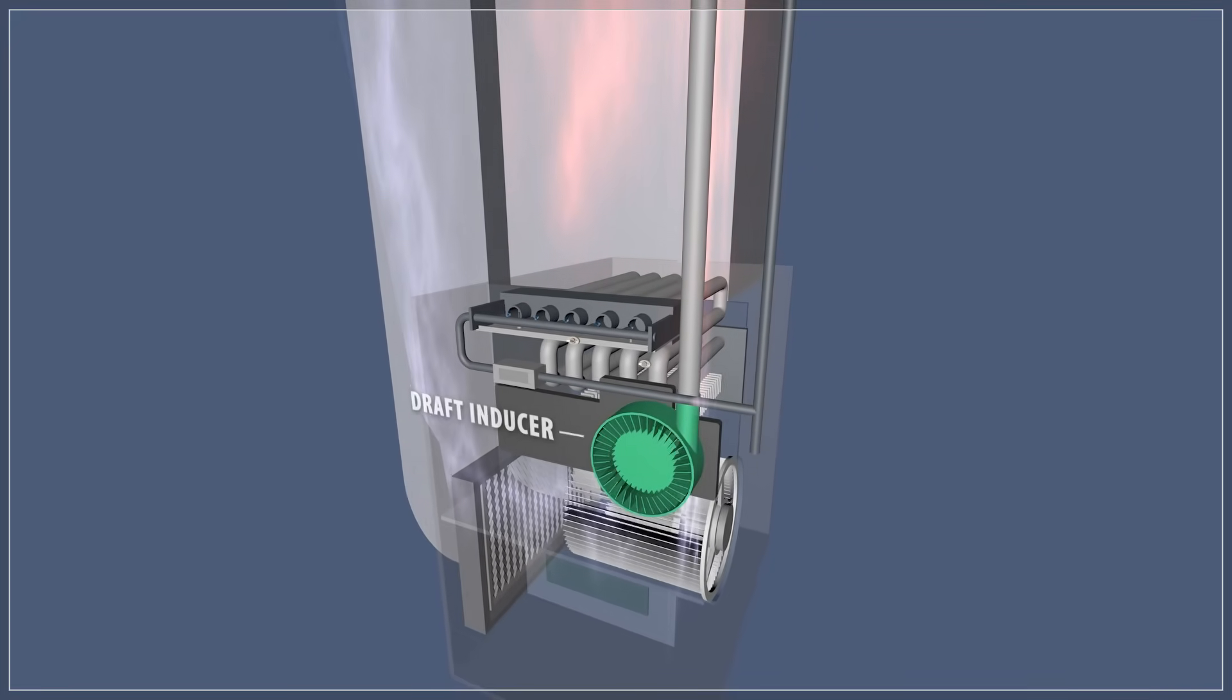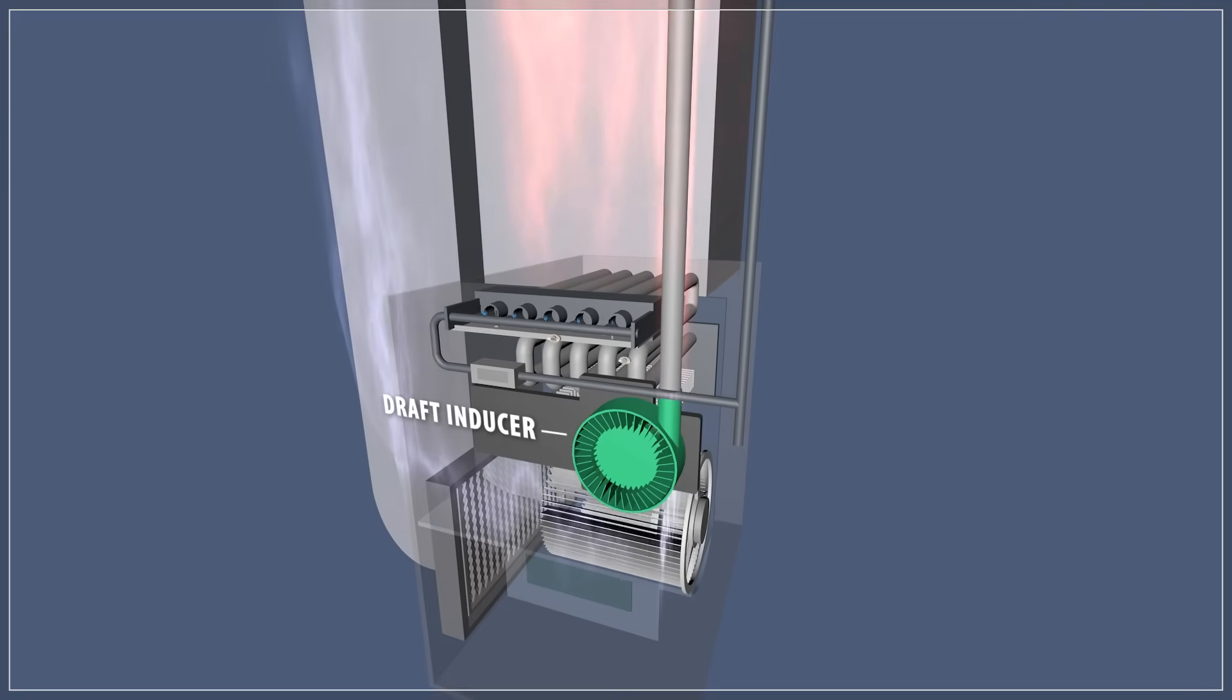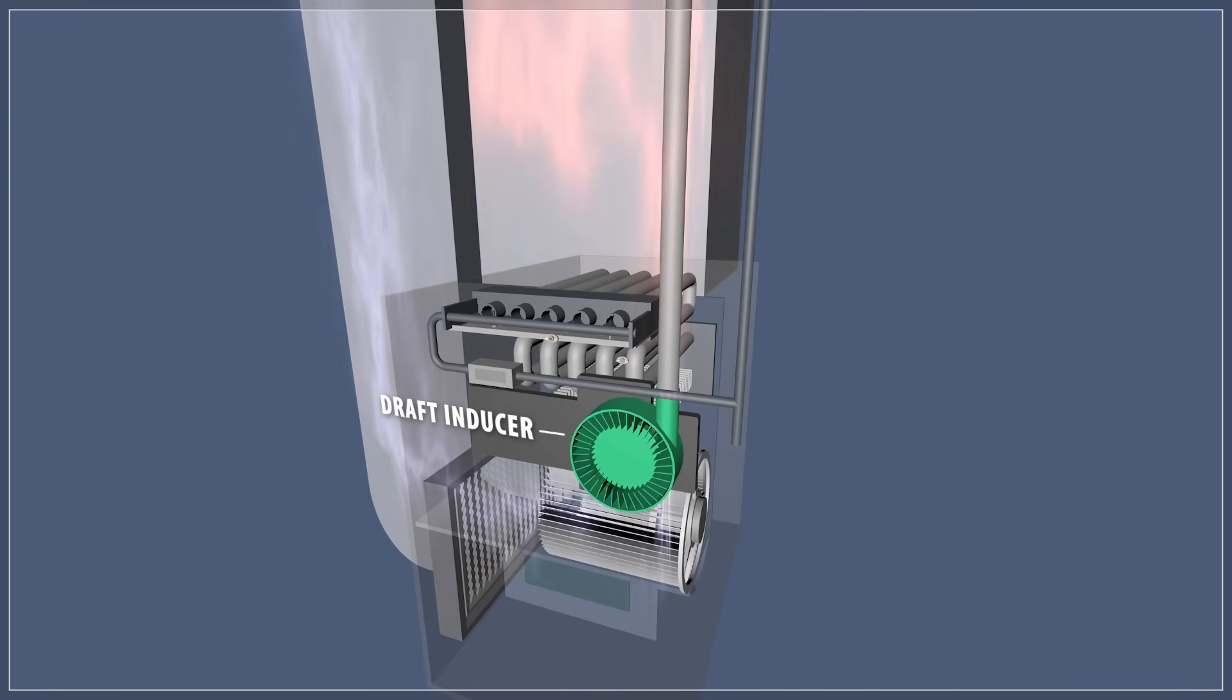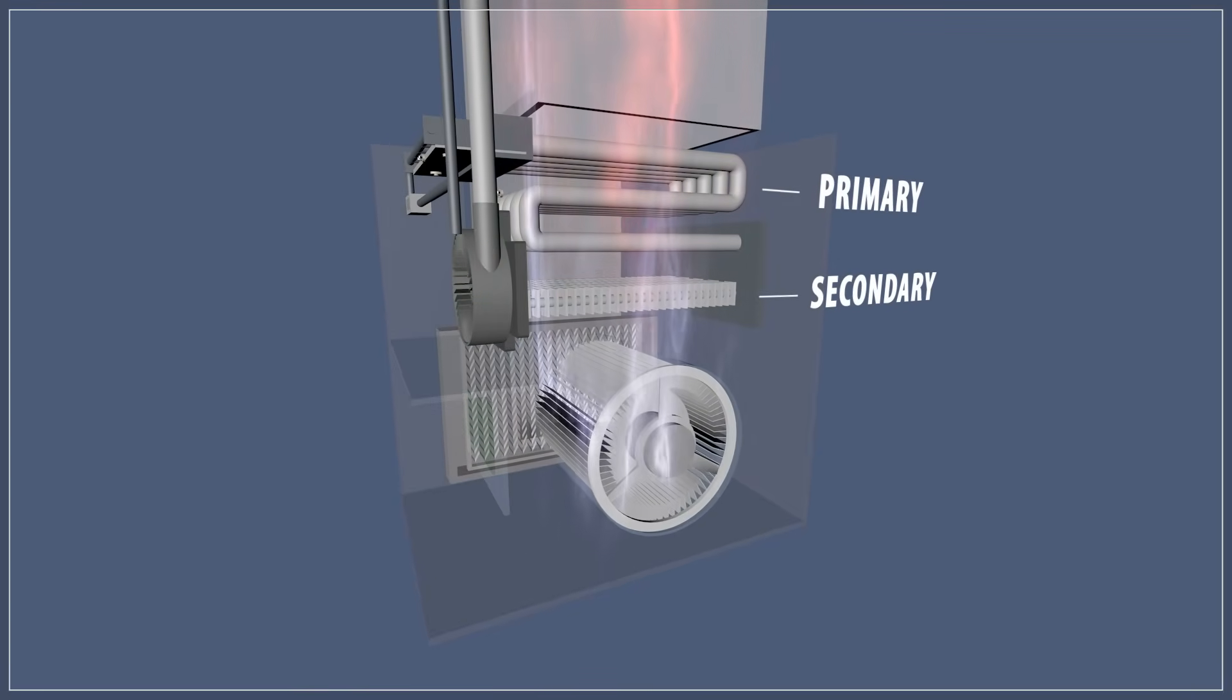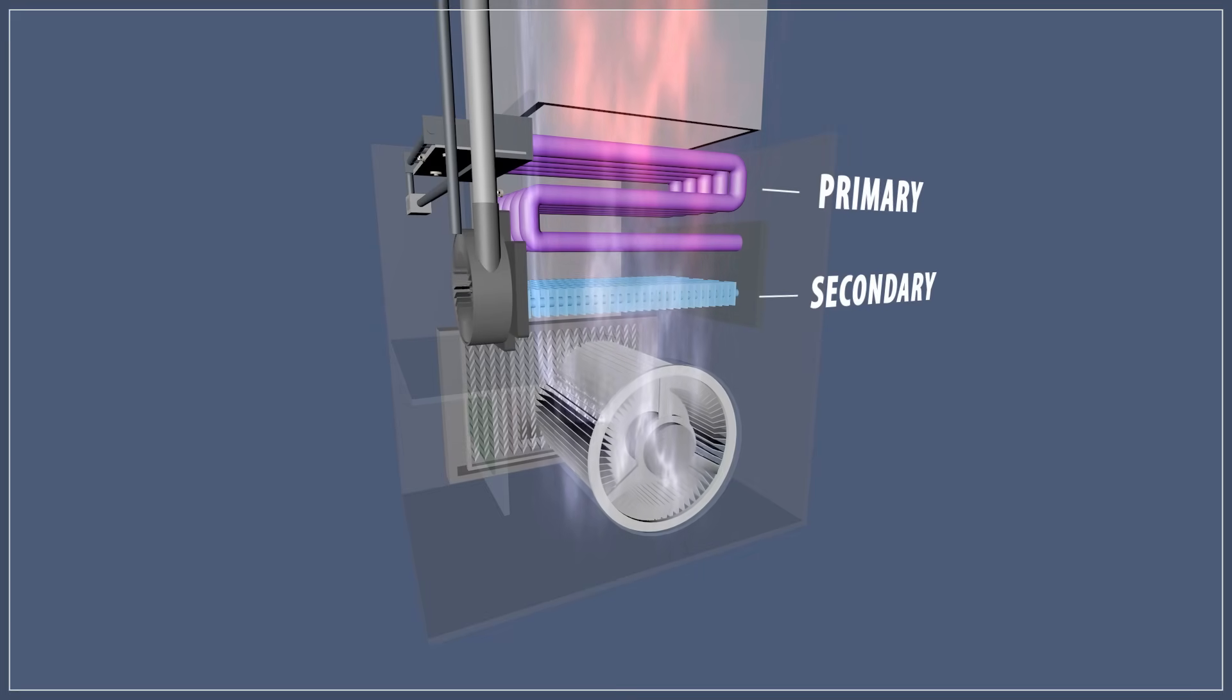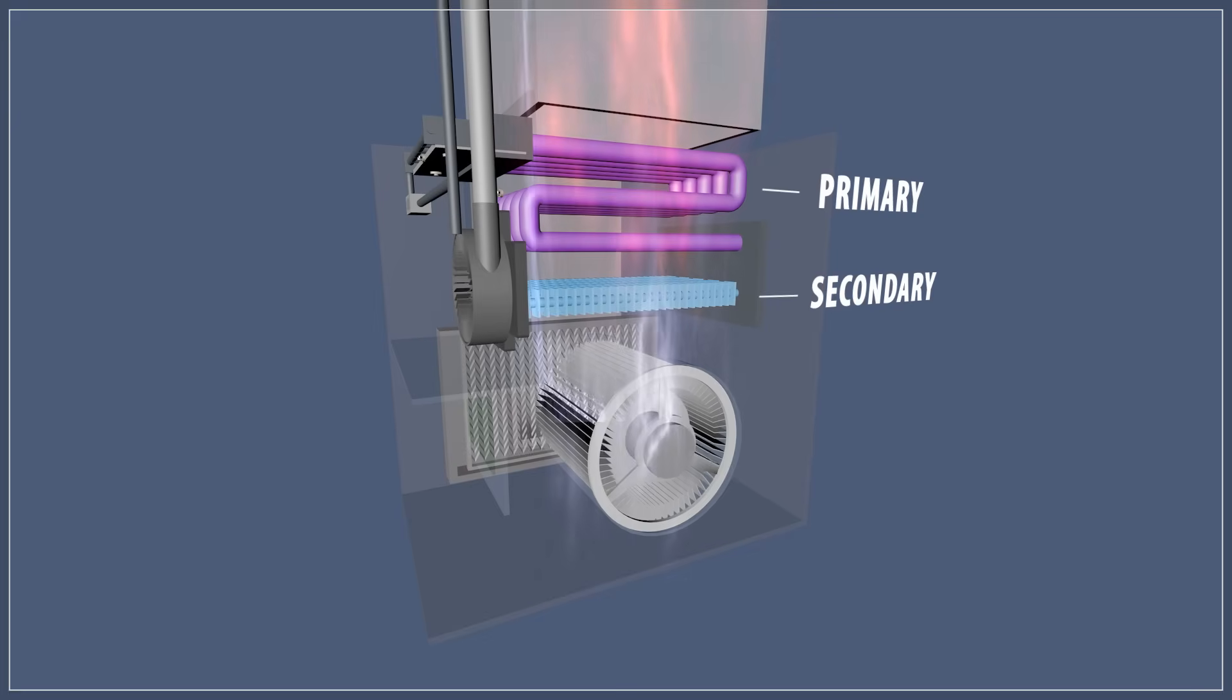Modern furnaces use a draft inducer fan to help exhaust the emissions. This forced draft also increases the efficiency. Condenser furnaces use a dual heat exchanger to condense water vapor. This extracts even more heat out of the combustion.